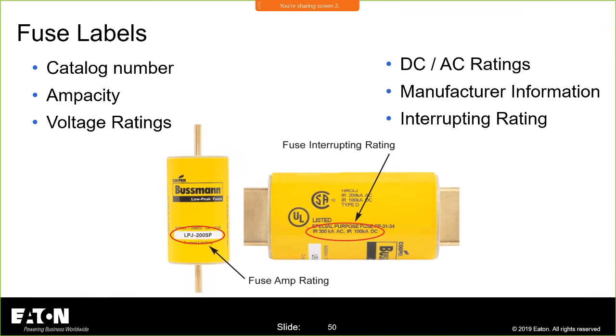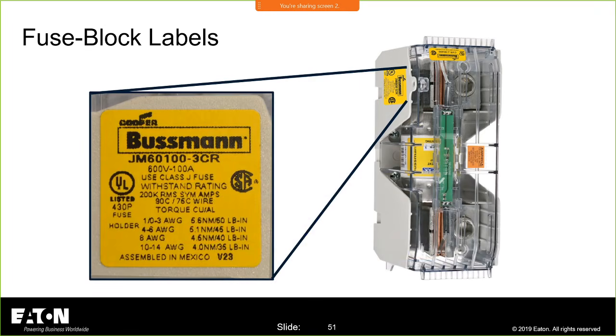Then you have your labels. You're required to put labels on there. You have to have your ampacity, your voltage ratings, whether it's applicable on DC and AC, and your interrupting ratings may be different on DC versus AC. All of your manufacturer, your catalog number information, and then your holders will have to have the same type of labeling on them as well. And you'll notice this one has a cover for finger safe, and then there's an LED right here on the front that tells you when it's open that is the fuse that has given its life to provide the protection to your equipment.